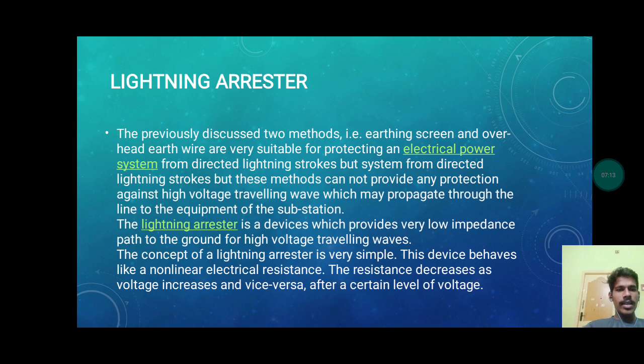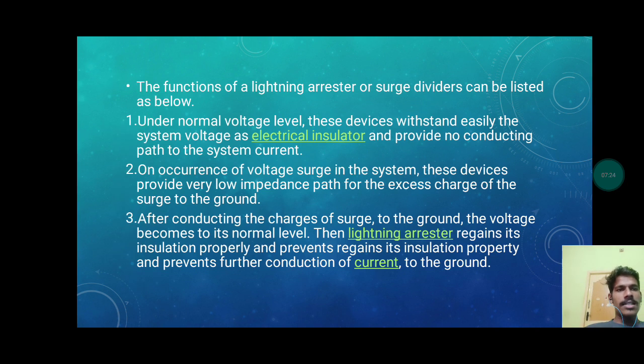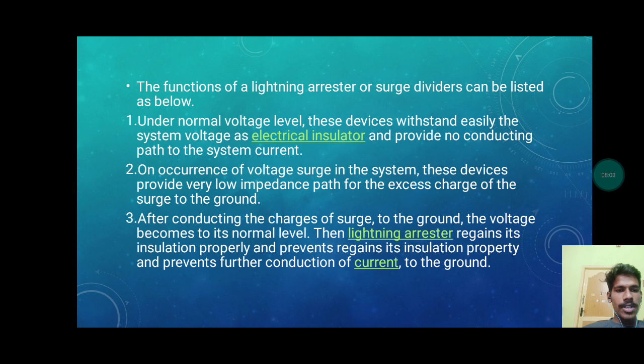The device behaves like a non-linear electrical resistance. The resistance decreases as the voltage increases beyond a certain level of voltage. The functions of lightning arresters or surge dividers can be listed as below. First point: under normal voltage levels, these devices easily withstand the system voltage, act as an electrical insulator, and provide a non-conducting path to the system current. Second point: on the arrival of a voltage surge in the system, these devices provide a very low impedance path for the excess charge of the surge to the ground. After conducting the charge of the surge to the ground, the voltage returns to a normal level, and the device restores its insulating property and prevents further conduction of current to the ground.